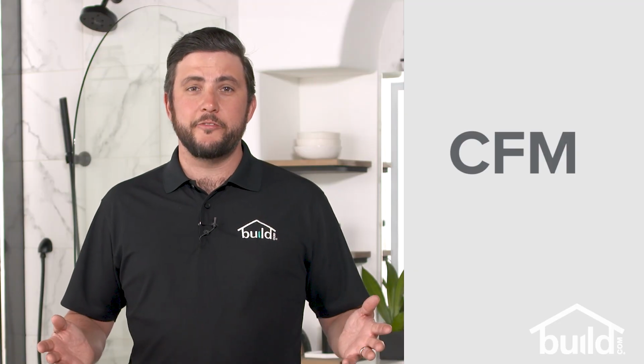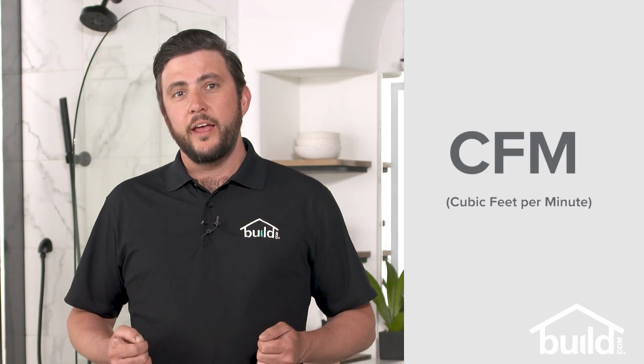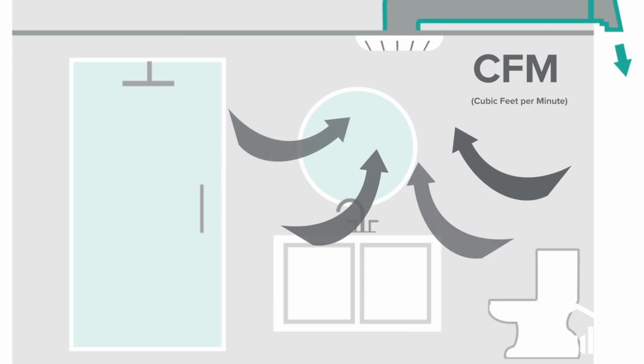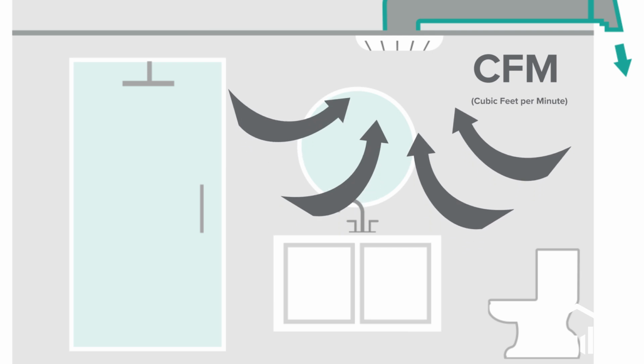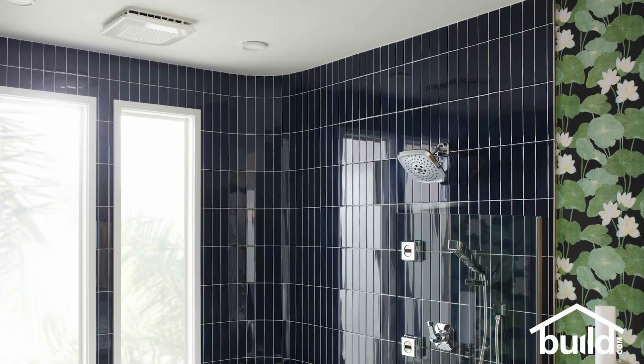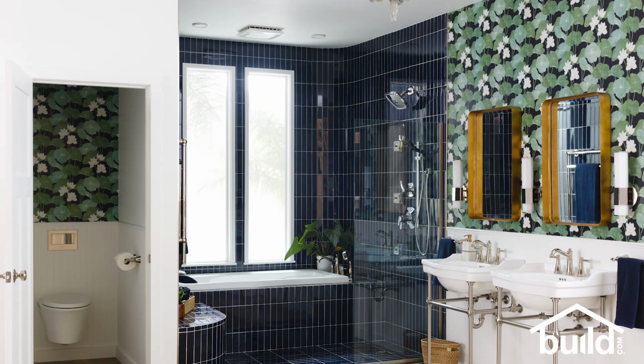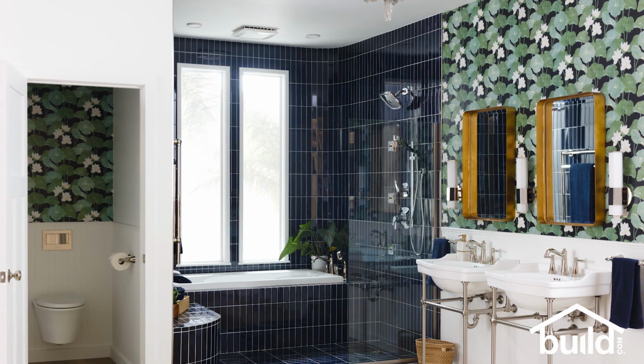Bath fans are rated by CFM, or cubic feet per minute, and this rating refers to the amount of air that a fan can move in 1 minute. Ideally, an exhaust fan will be able to move a room full of air about 8 times per hour, or about once every 7.5 minutes.